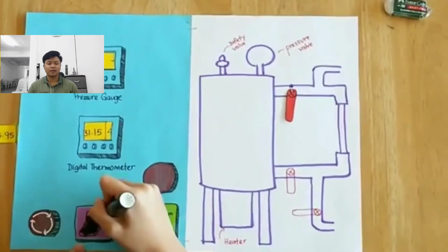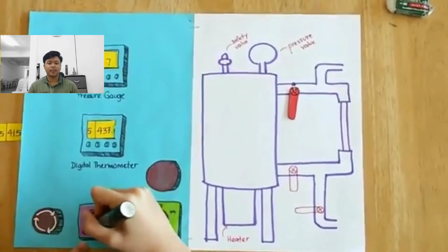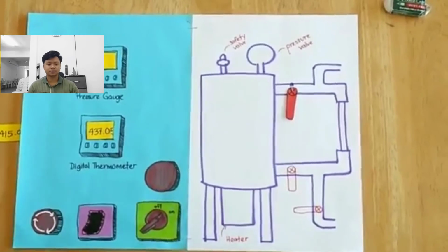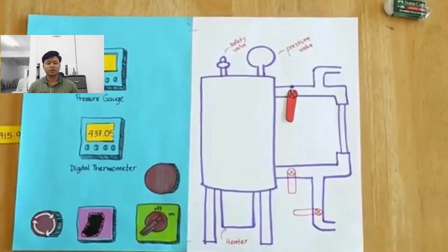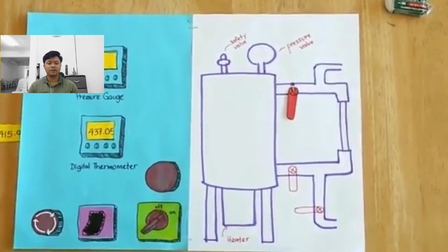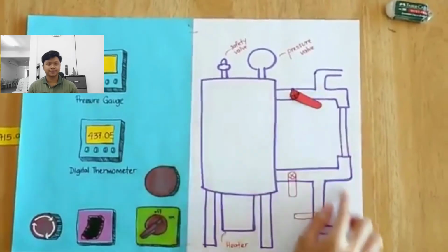Open the valve at the upper part of the sight glass, MVB 102, to release water. Open the valve at the bottom part of the sight glass and the valves MVB 104 and MVB 105 to drain out the water from the tank.